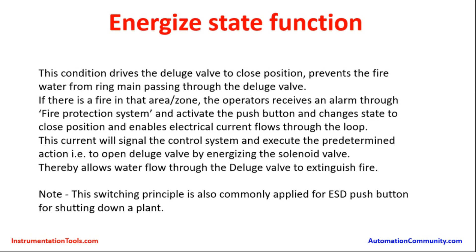Water gets admitted through the Deluge valve and goes to the respective area and zones, helping to extinguish the fire. Note: this switching principle is also commonly applied for ESD push buttons for shutting down a plant. Due to any fire or other emergency situations, there could be a requirement to operate an emergency shutdown push button for that area to get shut down or isolated. Those push buttons also have a normally open contact and are used for a similar application — whenever the push button is pressed, the current flows through it.